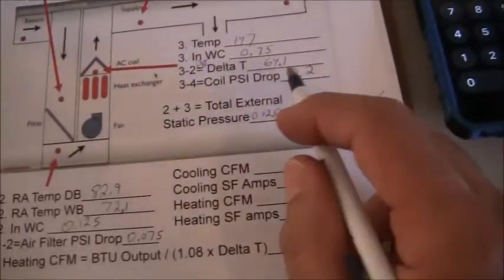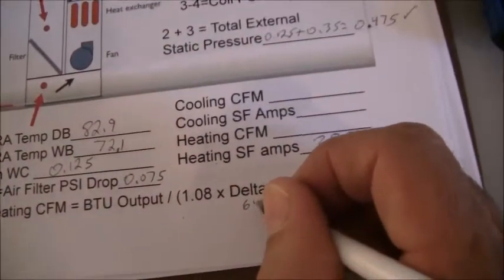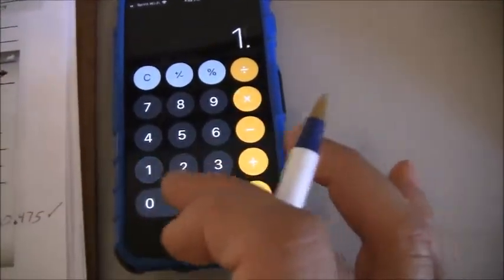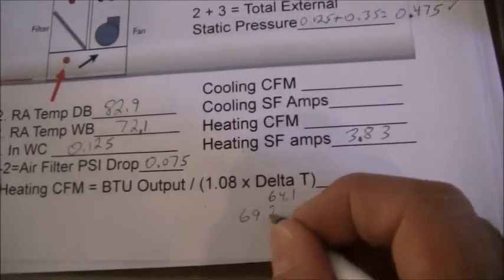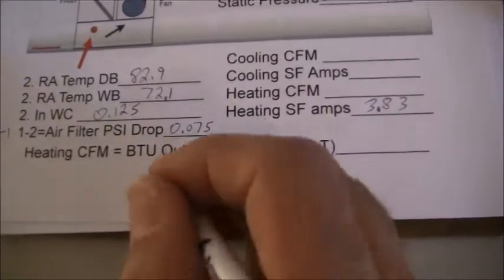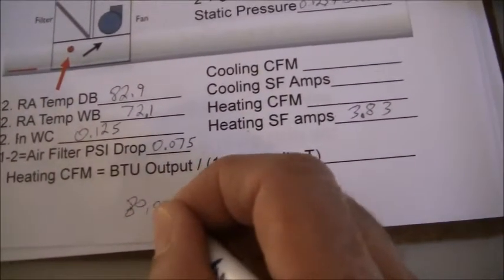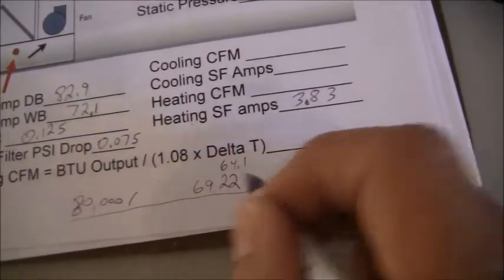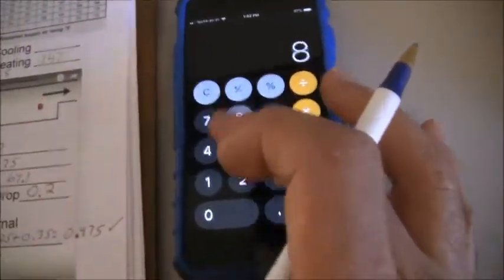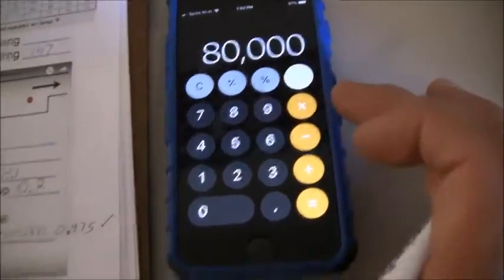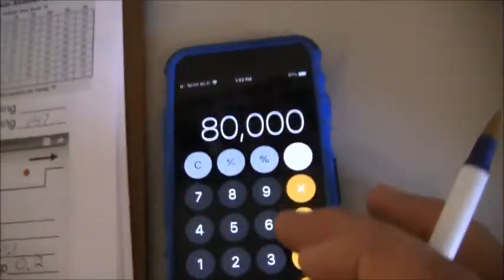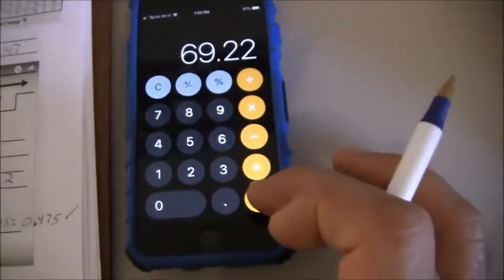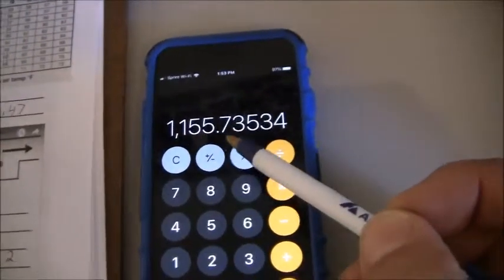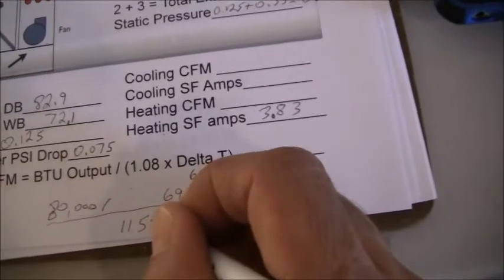Now we know that the delta T is 64.1. We're going to multiply that by 1.08. That is going to equal 69.22. We need the BTU output. We know that's 80,000. We want to divide that number by 69.22. So we take 80,000 and divide it by 69.22, which equals 1155 CFM.